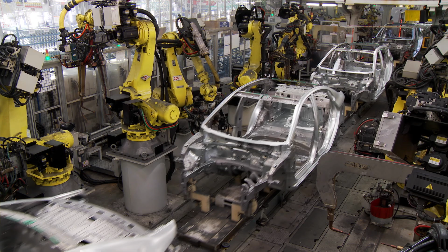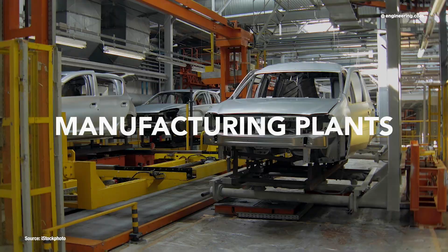This week's Industrial Automation Word of the Week is an acronym, SCADA. SCADA stands for Supervisory Control and Data Acquisition. It's a system used to monitor, control, and collect data from industrial processes such as manufacturing plants, water treatment facilities, electrical grids, oil and gas pipelines, and building automation systems. It typically consists of sensors, actuators, and PLCs or RTUs to collect data from field devices and execute control logic. It's all connected through a network using Ethernet, fiber, radio, cellular, or industrial protocols. SCADA software runs on servers and operator workstations and displays process information through HMIs. SCADA, Supervisory Control and Data Acquisition.